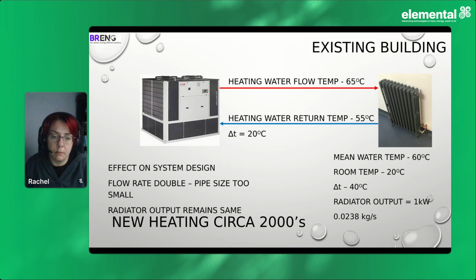But again, a true audit of the school will determine what is the actual output of that radiator required for that current mode, not when it was first installed. Is that pipework suitable for reuse, or do we need to replace it? What you would generally find is once the thermal improvements have been made, that radiator or heat emitter will probably be big enough to heat that room. But it's the actual pipework to that radiator that may need changing.